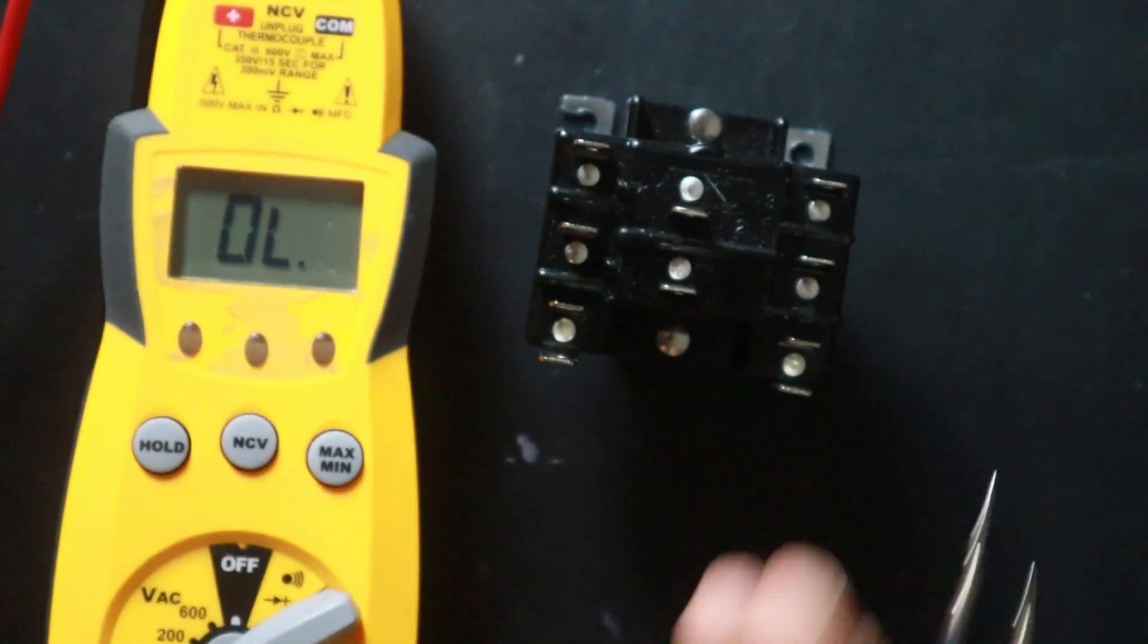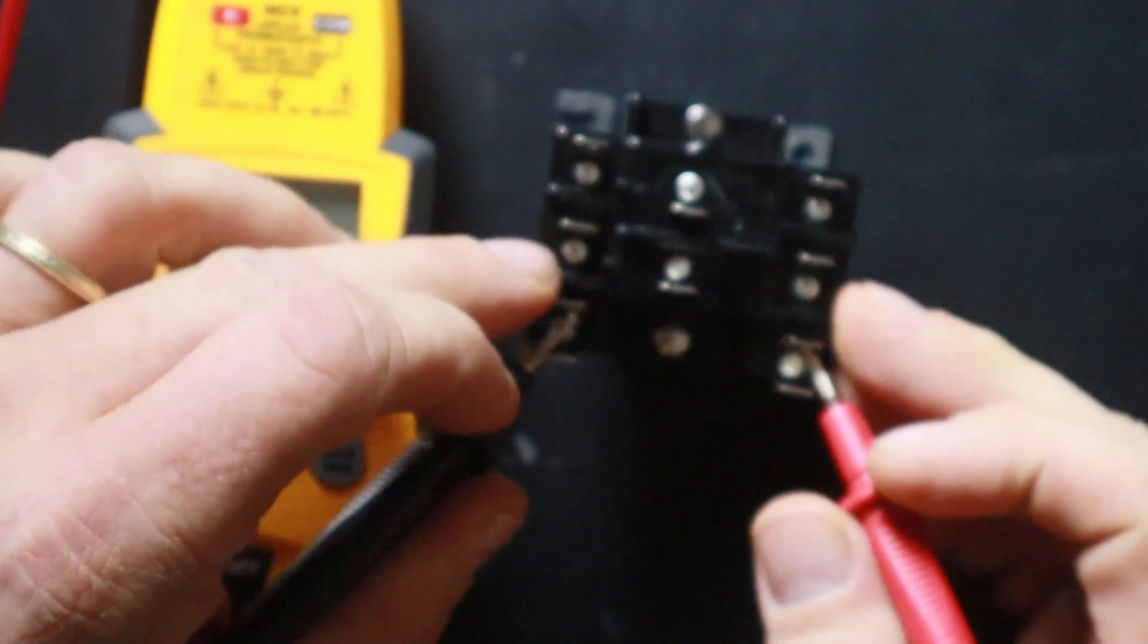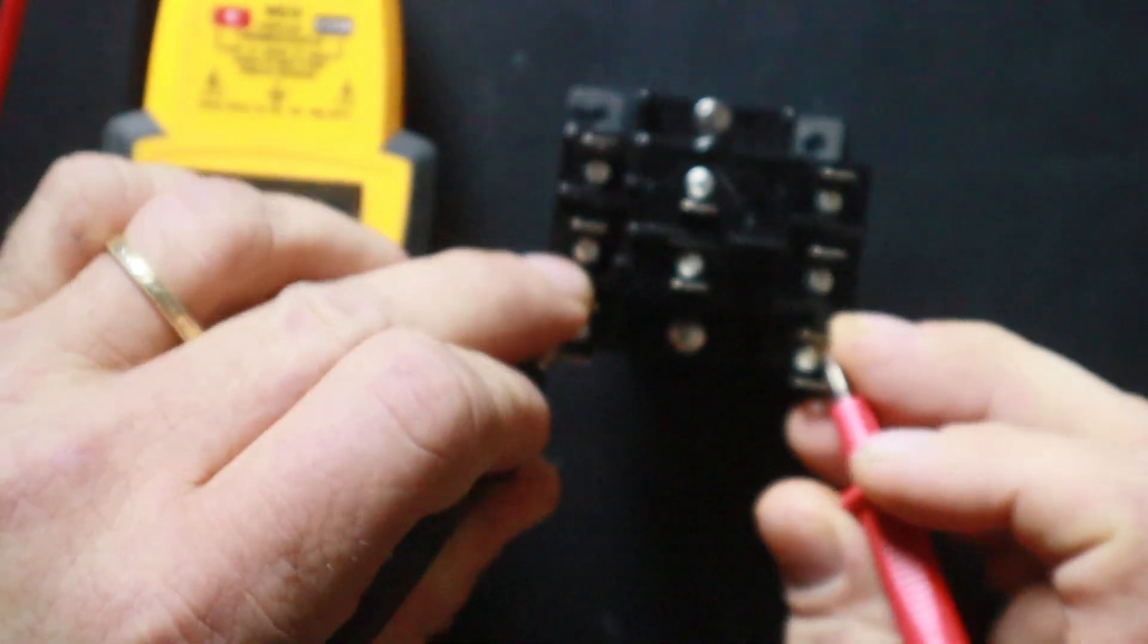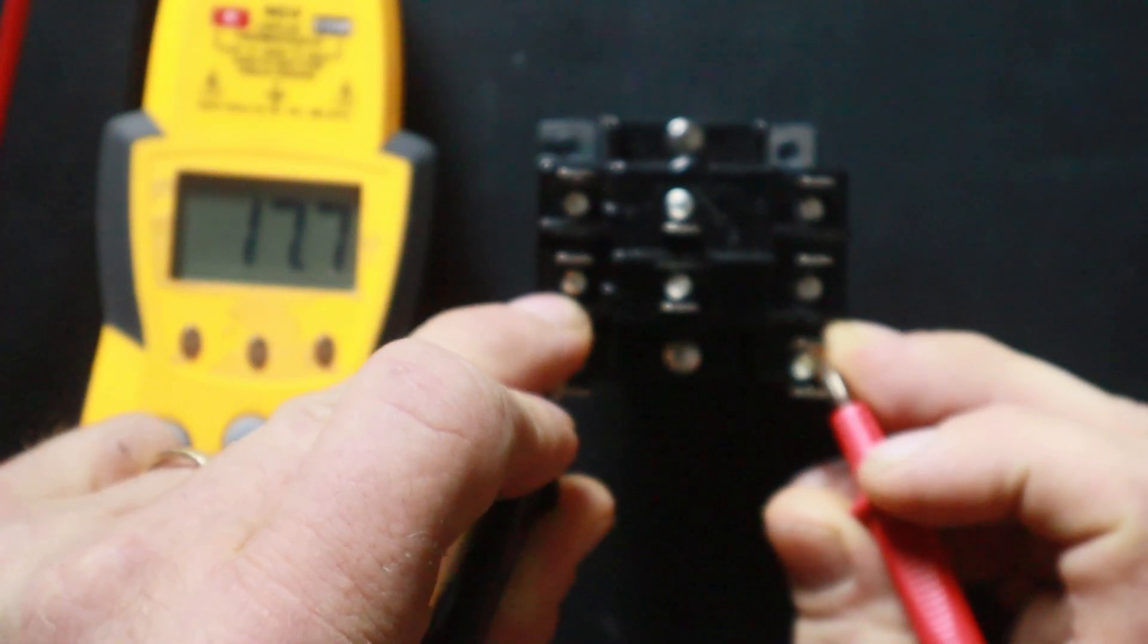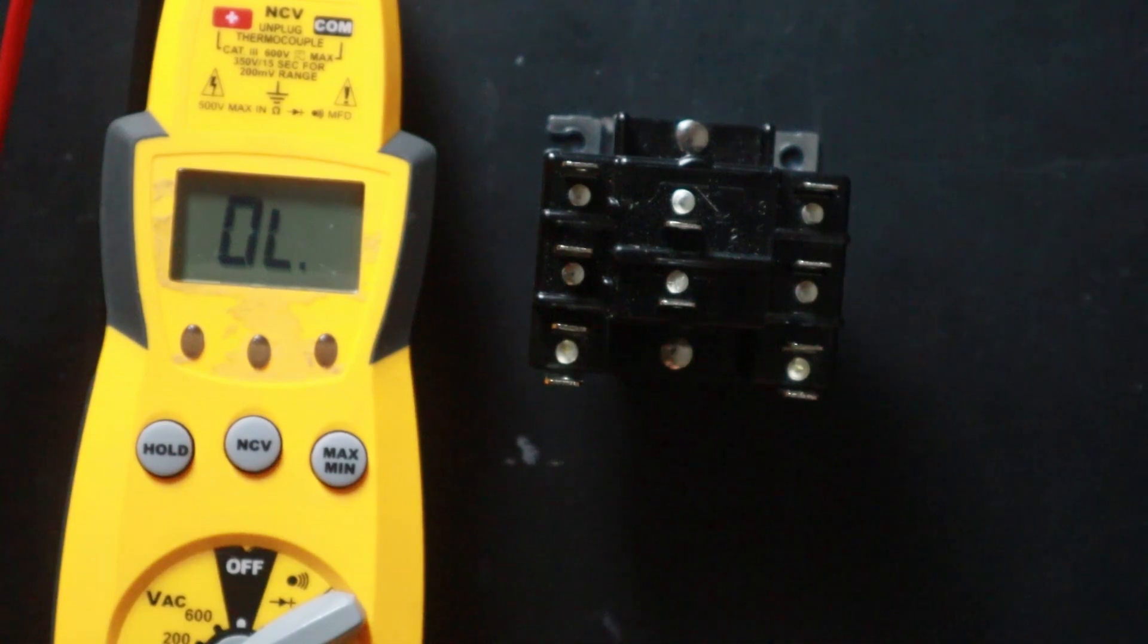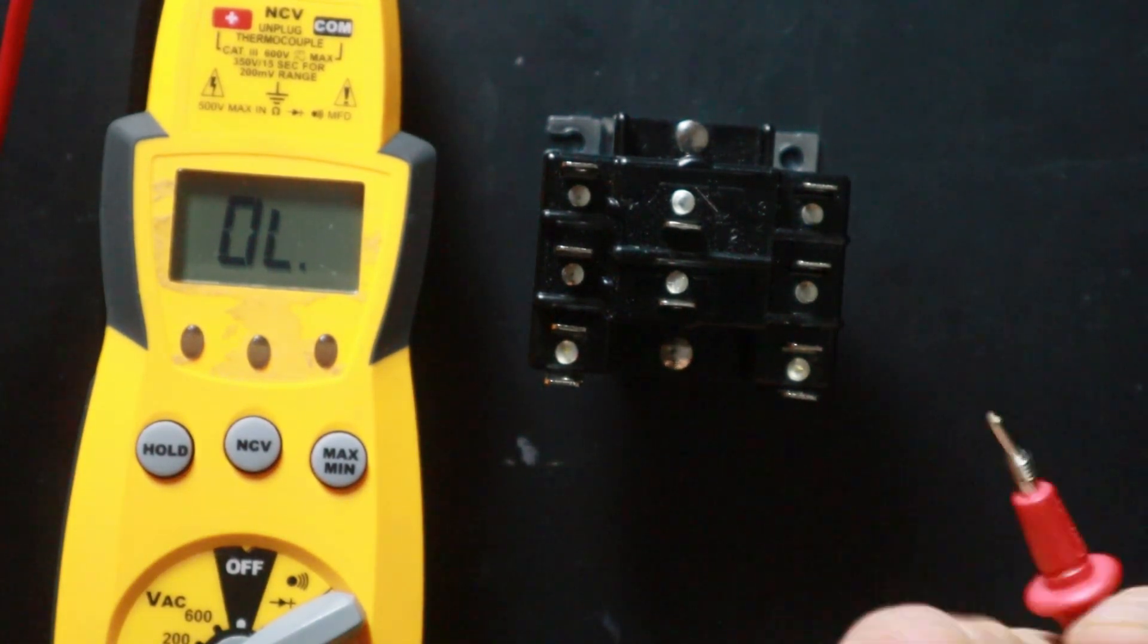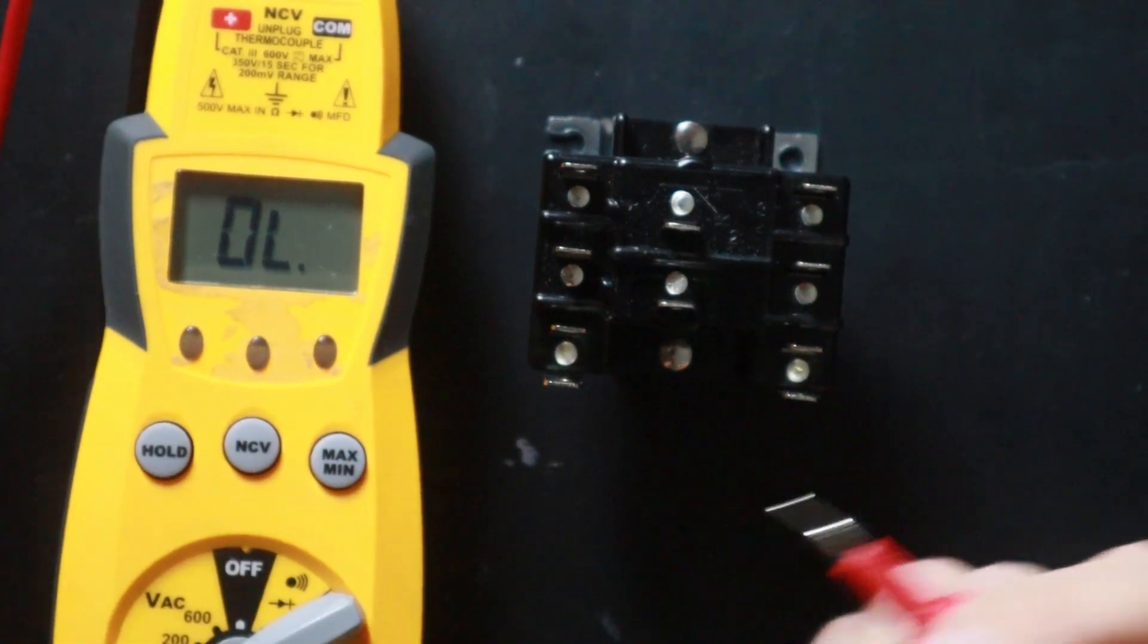So when you're taking ohm readings and you're ohming out a coil, for example, I find generally I usually find between 10 and 20 ohms. So you can see here on this coil, I'm reading 17.7. So that's pretty typical of a lot of relays I work with in HVAC. Once again, it's going to be manufacturer specific. So you do want to look these things up or at least test enough of them to get an idea of where they should be.